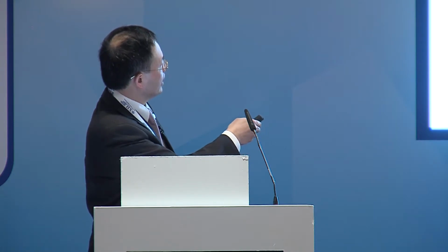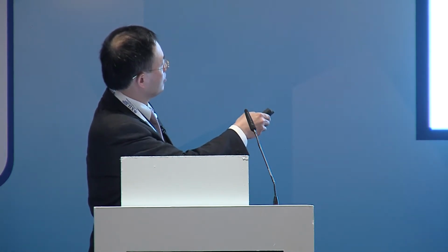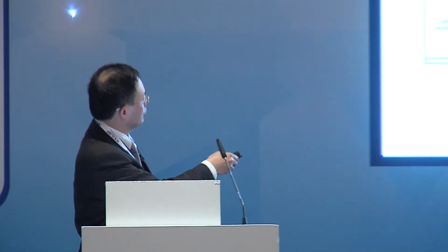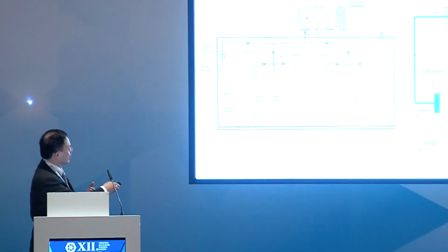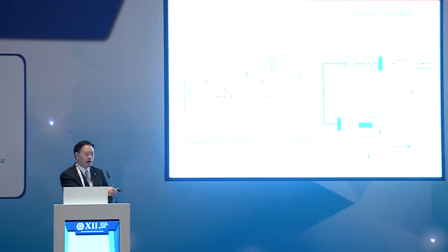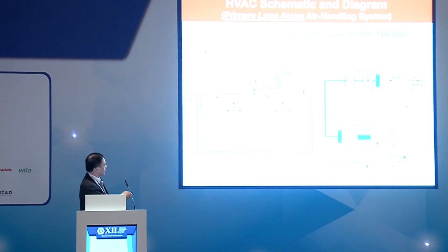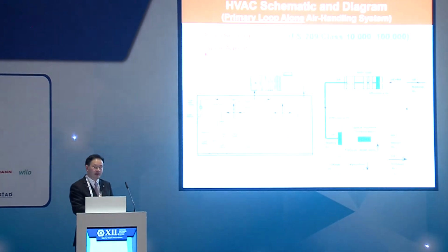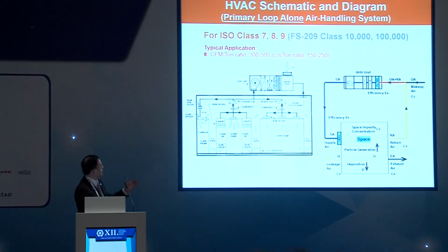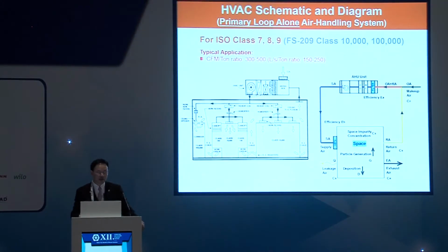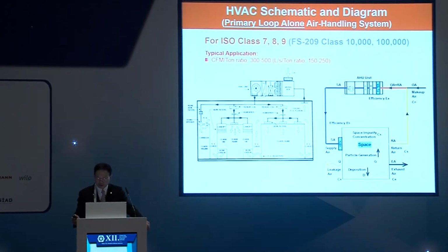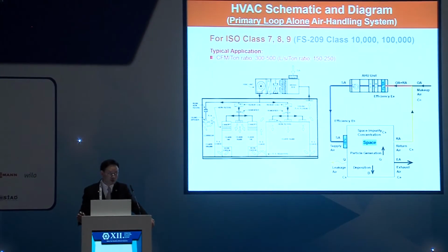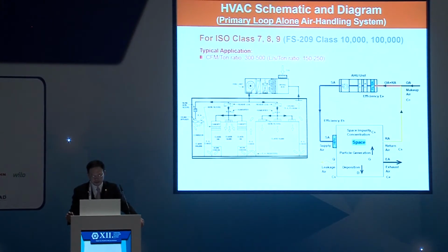If you look at the real diagram, you may have different class clean rooms. You may share a common return air. Return air in the ceiling is drawn into the air handling unit and merged with the outside air and the supply air. You can do a reheat, you can do a humidification, then you provide the required air properties to the clean rooms to achieve heating, cooling, ventilation, and air cleanliness requirements. So this is for the low-end clean rooms. This is a typical configuration, which is not much different from commercial buildings or spaces.